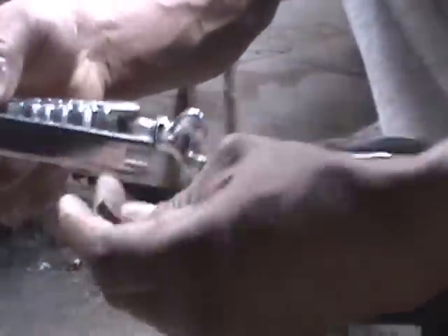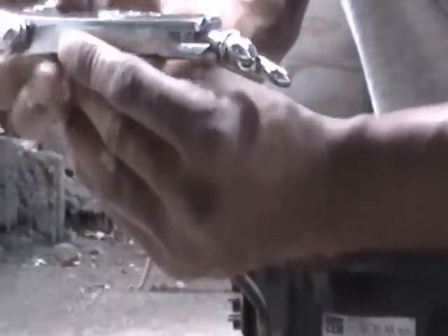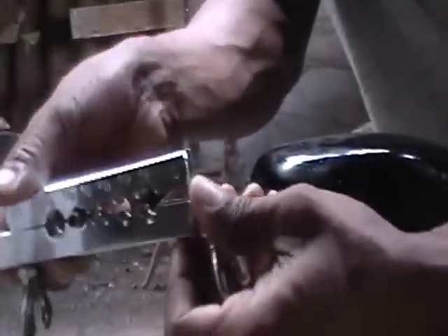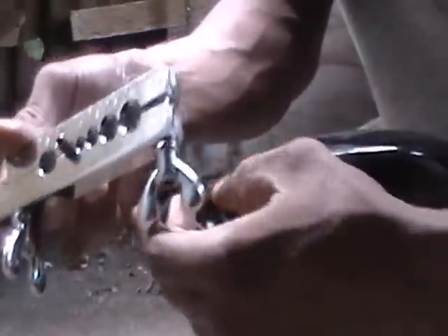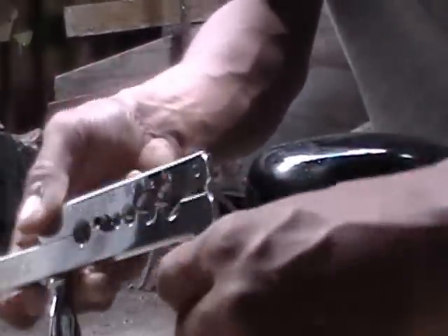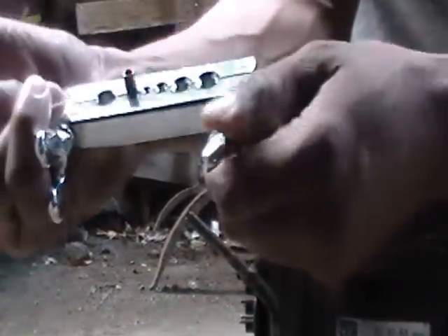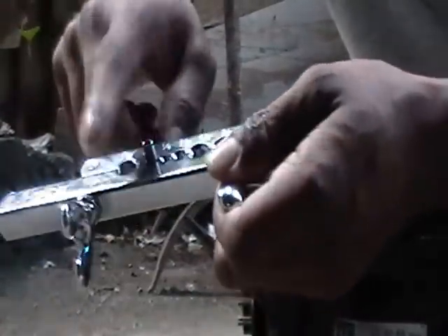I'm going to swage it now. My block right here — this is quarter inch. You fit it in there and pull it to about there. The rule is that you tighten the end of the block closest to the pipe you're going to swage. All swaging is, is opening a pipe to a diameter to fit a tube of the same diameter into that pipe. I'm making it wide enough to fit the outside diameter of an actual quarter-inch tube into it. That's all swaging really is.